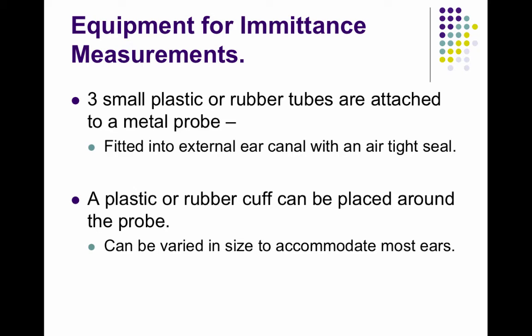There's a probe with three open tubes. It's fitted tightly in the ear canal — you have to get a seal — and there are different sized tips based on whether you're working with a child or an adult.